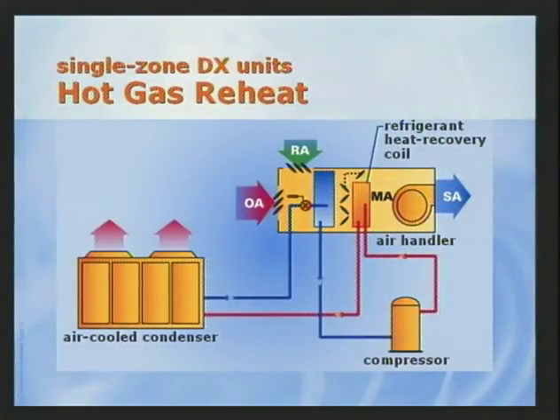Now, using heat that is recovered from the refrigeration cycle of the DX unit can reduce system operating costs by avoiding the use of new energy reheat. This is typically accomplished by adding a heat recovery coil to the refrigeration circuit. This coil transfers sensible heat from the hot refrigerant vapor to the supply air downstream of the cooling coil. Again, this may also allow the system to meet local codes and ASHRAE's Standard 90.1. However, if not factory engineered and factory installed, use particular care when selecting the heat recovery coil or installing the refrigerant piping and controls. Failure to do so could cause compressor lubrication problems.